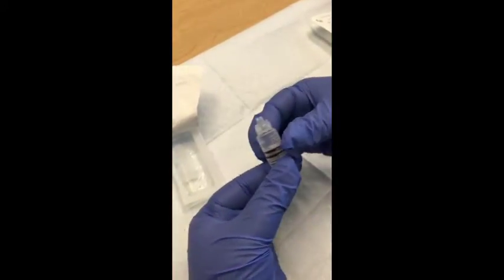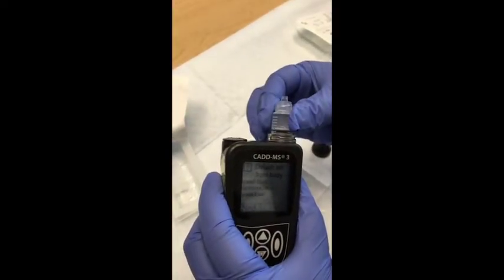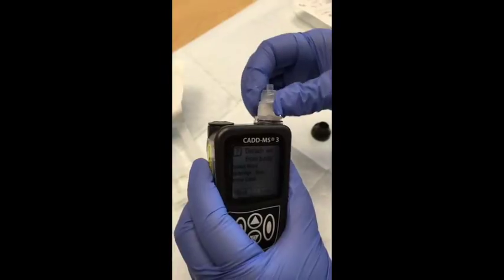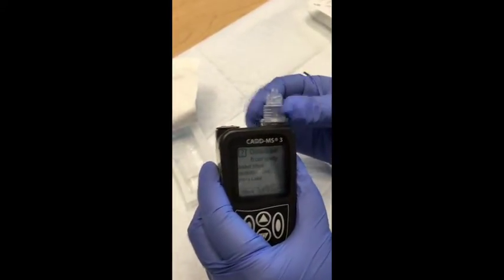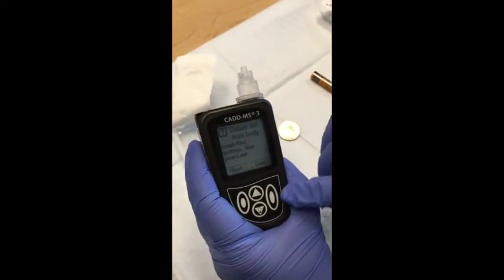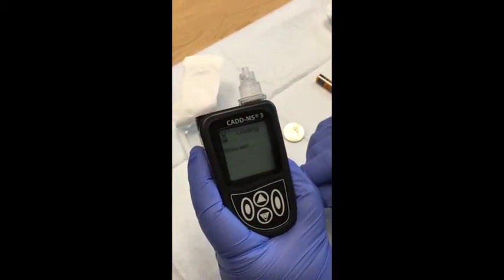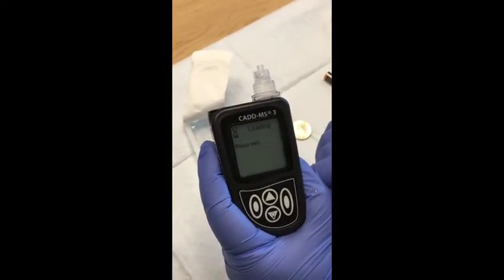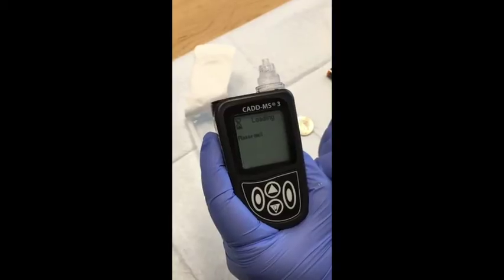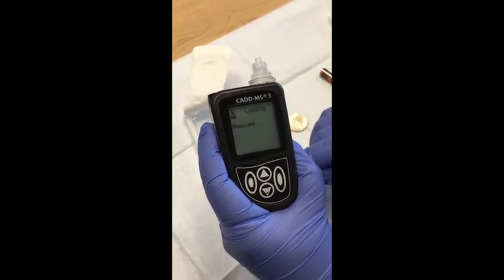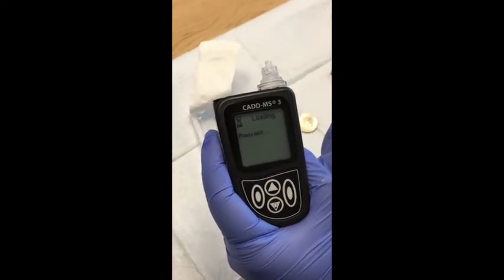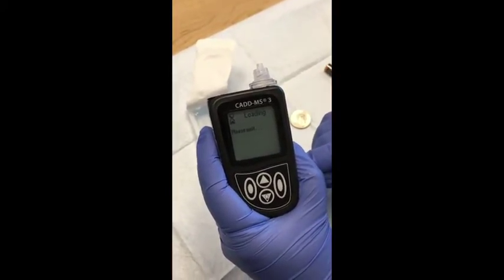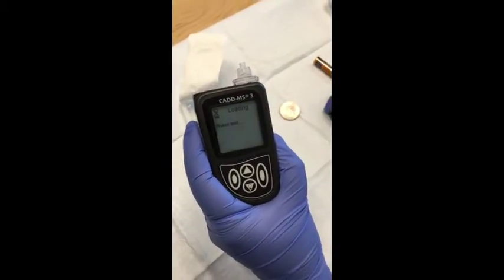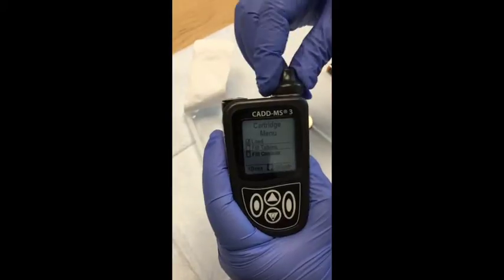Now you're ready to load it. So go ahead and take your syringe. Make sure that again it's a 3cc syringe. Take off the plunger and put it inside. And then turn it clockwise a quarter turn to secure in place. Go ahead and press load. There shouldn't be bubbles in there, but that's okay. Okay, so go ahead and put the syringe cap back on.